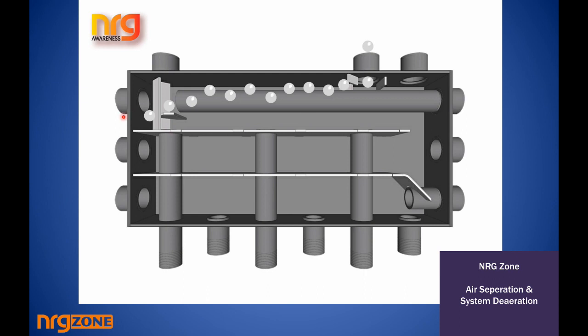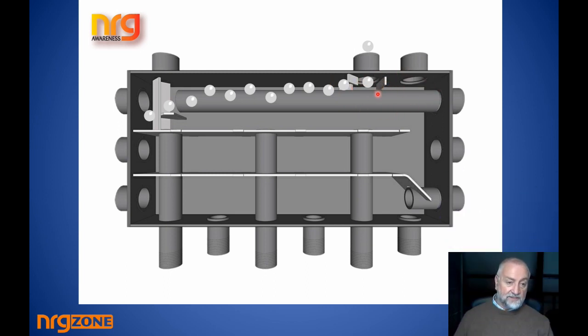If you see, I'm now saying that if the water slowed in the top chamber, the air rises to the top of that chamber. There's a sequence of baffles over here that funnel the air out through the middle of the 3 connections on the top, and that would be the opportunity, the best place to take air away. Once the air gets funneled in towards this socket, there's another baffle that kind of blocks it here. If it happens to make its way over that because there's so much air in the system, well, so what? There's gaps on the left and right hand side of this back baffle that let it flow back and still go up the vent chamber, so it makes no difference.